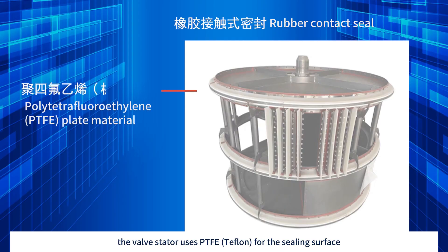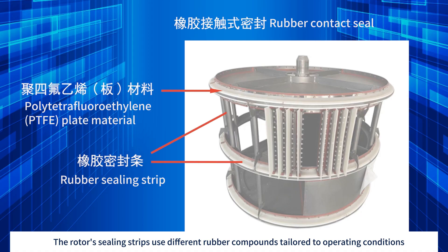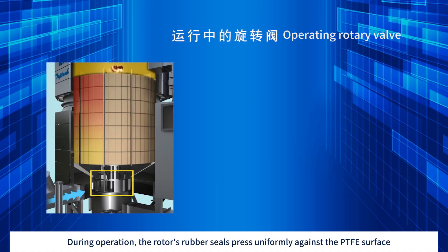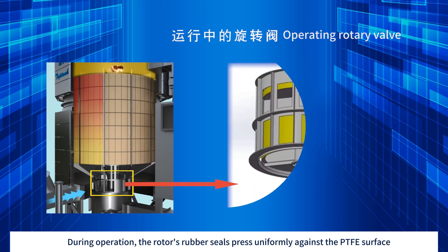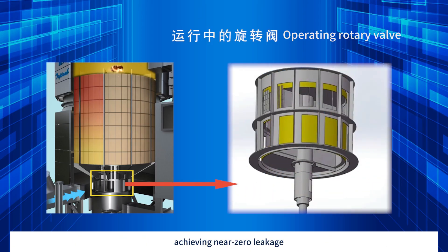With rubber contact sealing, the valve stator uses PTFE Teflon for the sealing surface. The rotor's sealing strips use different rubber compounds tailored to operating conditions. During operation, the rotor's rubber seals press uniformly against the PTFE surface, achieving near-zero leakage.